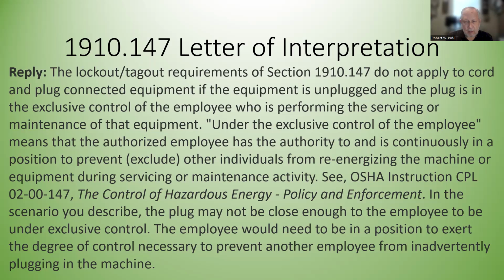Policy and enforcement. I'm going to read it. In the scenario described, the plug may not be close enough to the employee to be under exclusive control. The employee would need to be in a position to exert the degree of control necessary to prevent another employee from inadvertently plugging in the machine. So OSHA's getting kind of strict on this, and they should be. It's an exception to the policy, and these restrictions should be enforced strictly. So they're saying it's kind of too general.